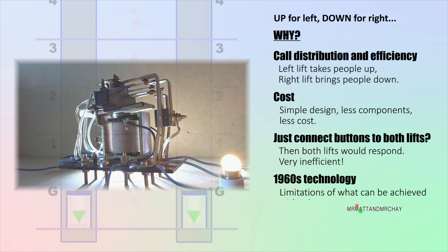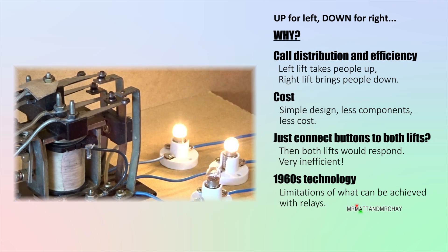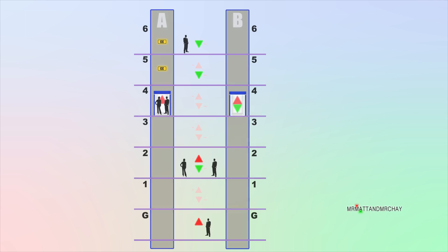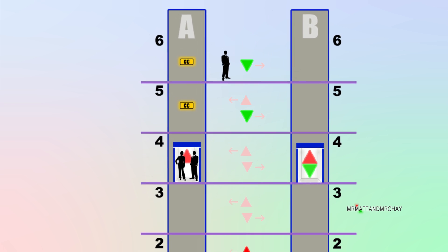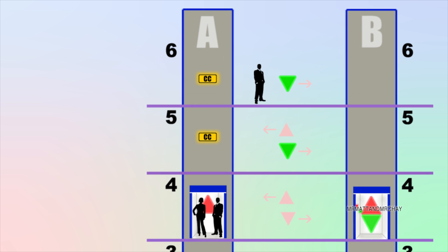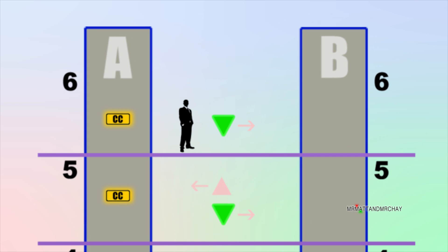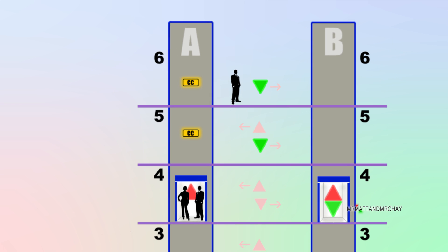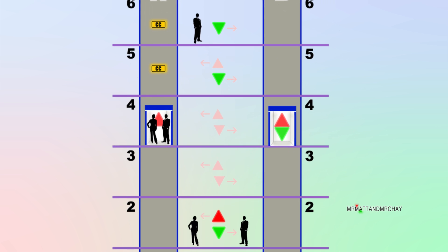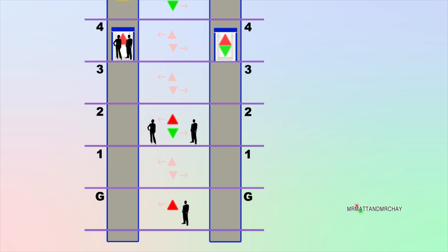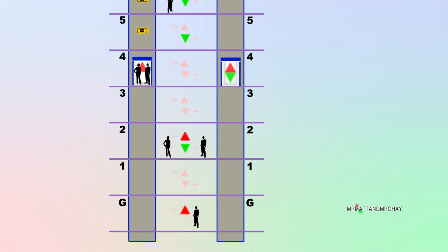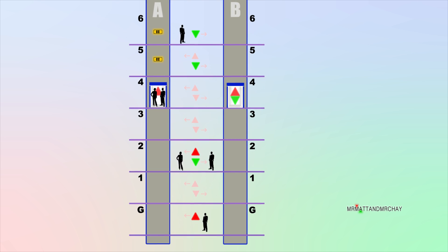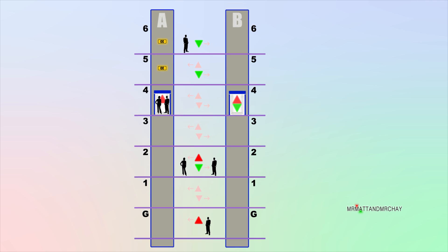This design was from the 1960s so there are limitations. So what's the answer here? Lift A has two car calls to make on the fifth and sixth floor. Then on the sixth floor there is a landing call waiting. It would make more sense for lift A to complete its journey upwards and collect the passenger on the sixth floor at the same time and then lift B to go in the other direction. Possible? Yes. But this would require a far more complex relay logic system. This is not what's going to happen here.